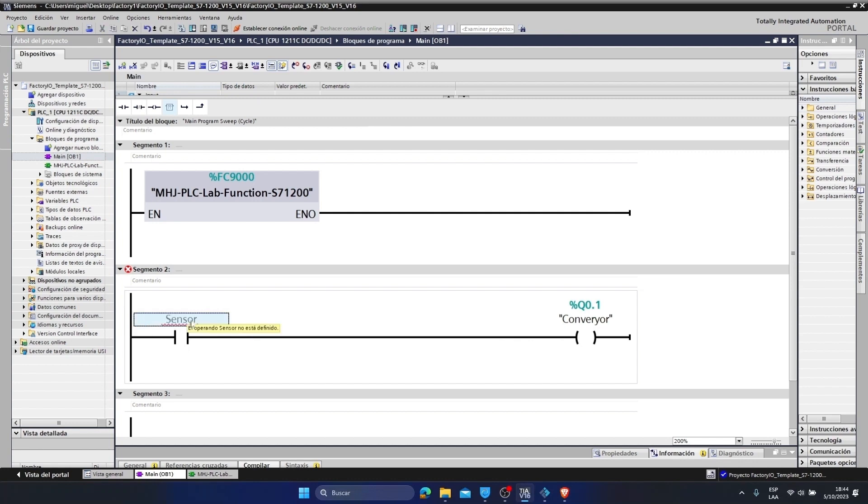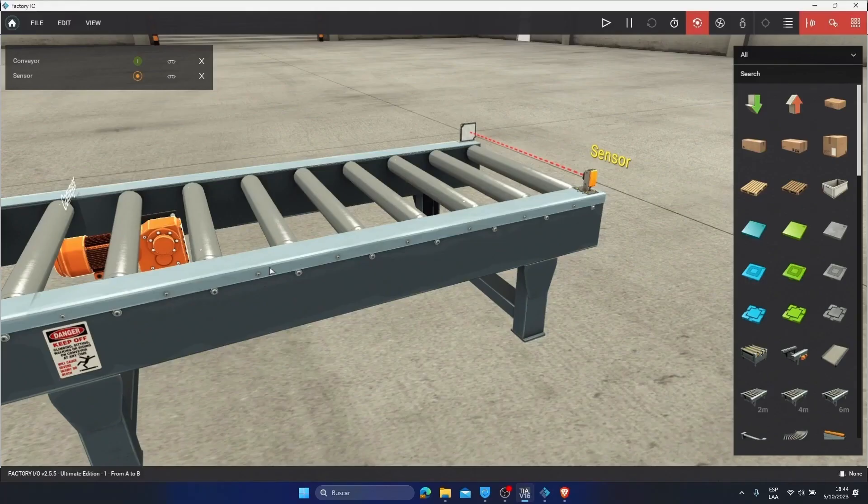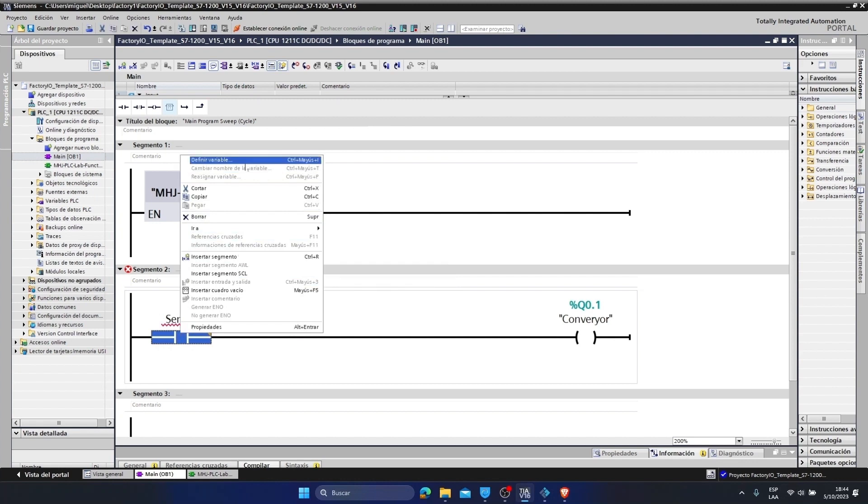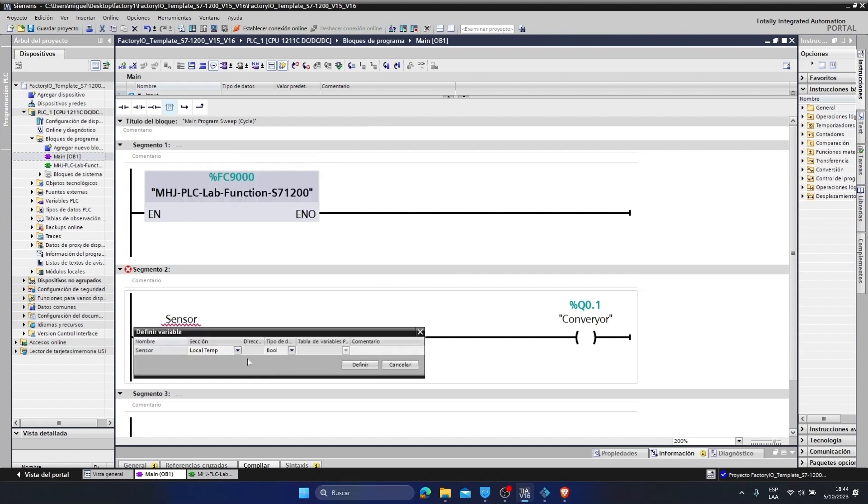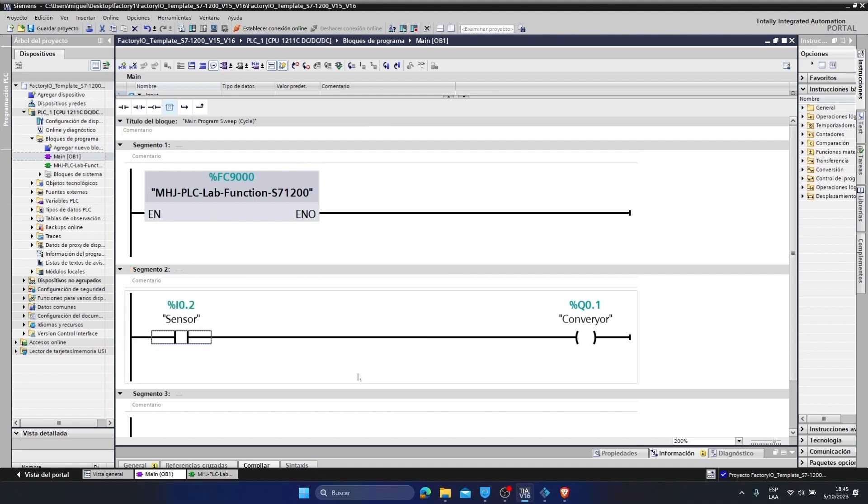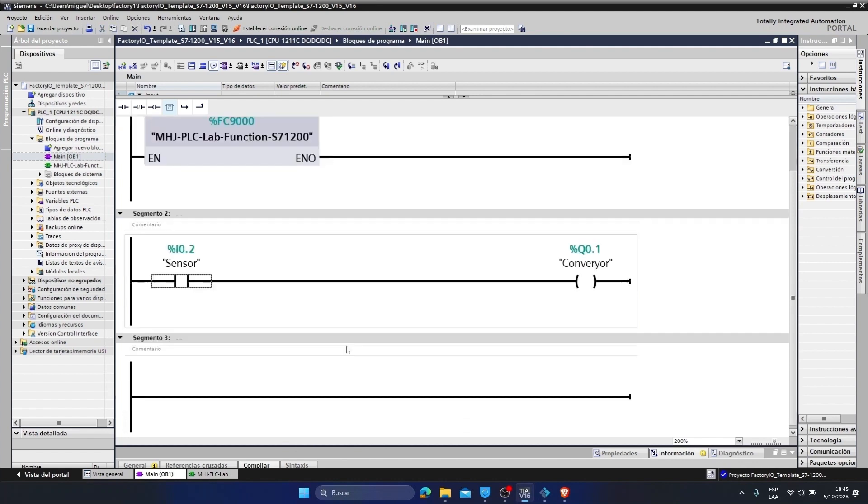As this sensor is always activated, it will close and our conveyor will turn on. It will move the box. And when it detects the sensor, it will open and our conveyor belt will turn off so that the object does not fall. We will define this variable as input. As you can see, we are declaring physical inputs and outputs of the PLC to be able to simulate it. And this would be our very small program to be able to control this small model.